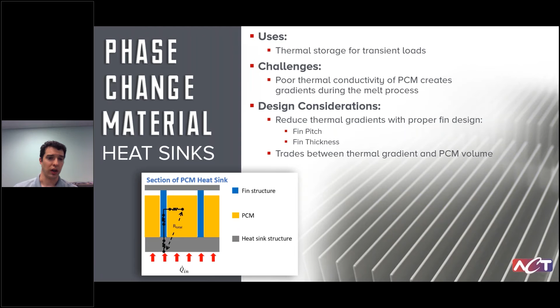Let's take a look at this case study. Here we have the design requirements: 10 watts being applied for 110 minutes over a 4-inch by 4-inch area, with a starting temperature of 60 degrees and a max surface temperature of 75 degrees.